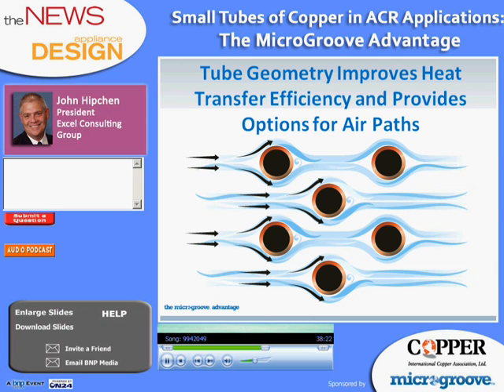On the refrigerant side, remember that the circuitry of the copper MicroGroove tubes can be modified to adjust refrigerant pressure drops. So a big advantage for MicroGroove tubes is the lower refrigerant charge. Aluminum microchannel tubes are all joined in a manifold, and that can take a considerable amount of refrigerant to fill.